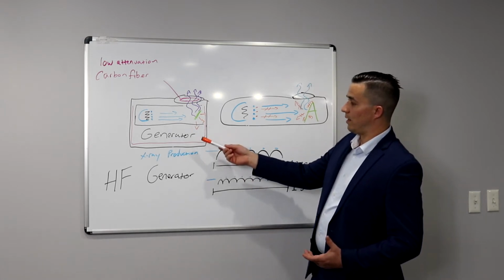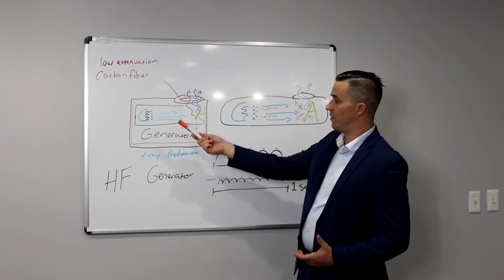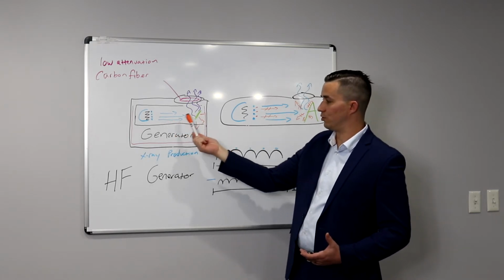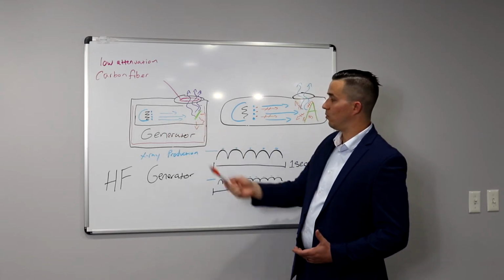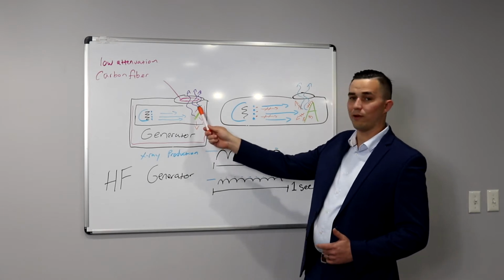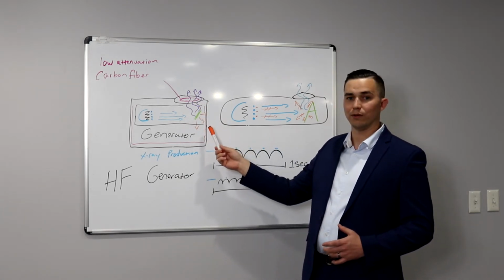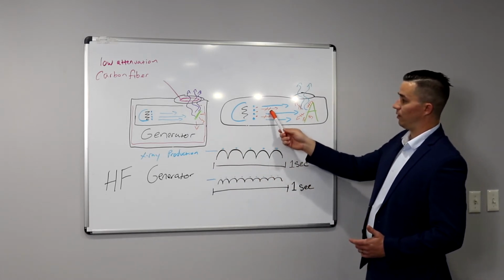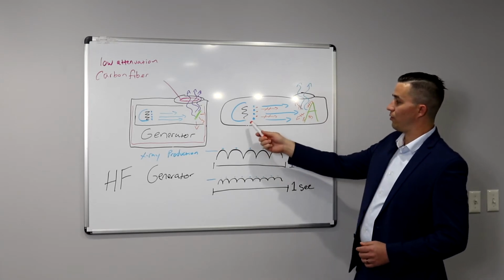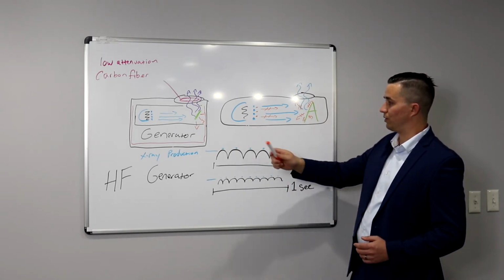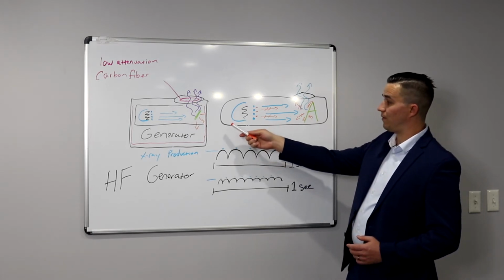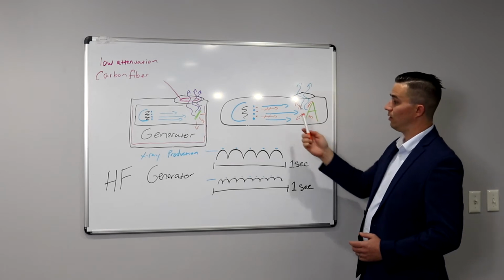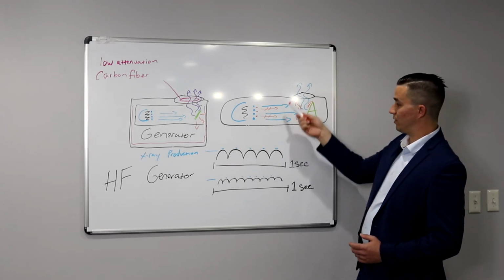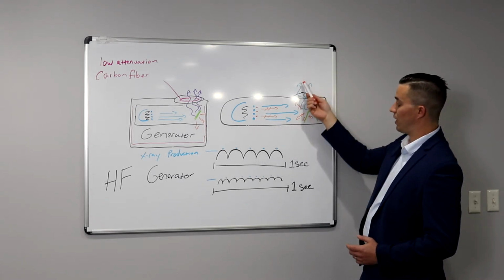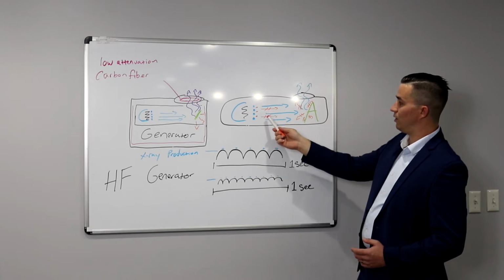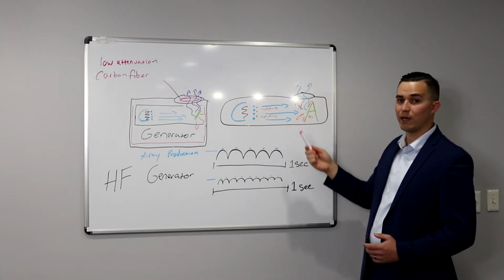So with that combination of the generator and our patented vacuum seal technology on our tube, which allows frictionless travel of electrons from cathode to anode, we're able to generate a much more amount of useful X-ray photons without generating as many low energy photons. Low energy photons are drawn here. So when the cathode boils off the electrons, electrons are determined by the amount of mA you put, and kV determines the speed at which they travel towards the anode. With our high frequency generator and frictionless tube, we're able to generate more useful X-ray photons and less of these unuseful X-ray photons that turn into scatter and leakage radiation.